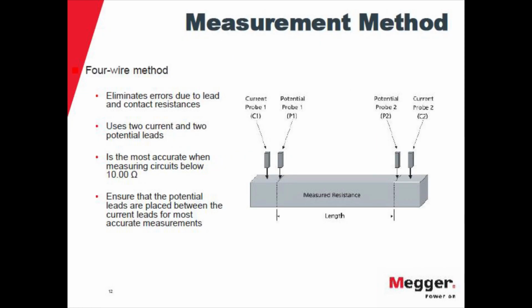So to get the proper measurement, to get an accurate value, basically you use what is called the 4-wire method. With this method you can eliminate the errors due to the connection or to the leads. Basically you have a current injection, leads, and separate potential probes. And this is the method that you use when you have to measure resistances below 10 ohms.